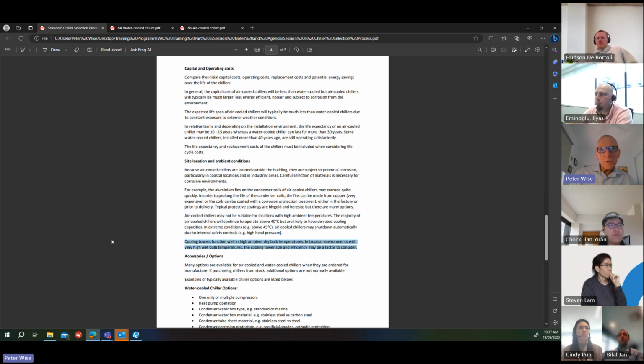Water-cooled chillers don't have the same problem. The cooling towers will function well in high ambient dry bulb temperatures. In tropical environments with very high wet bulb temperatures, the cooling tower size and efficiency might be a factor to consider. The cooling tower will get bigger because the approach that we talked about last week will increase, the size of the cooling tower will increase, and the efficiency will be reduced. But overall, it's going to keep running. So that might be the deciding factor if you've got high ambience.